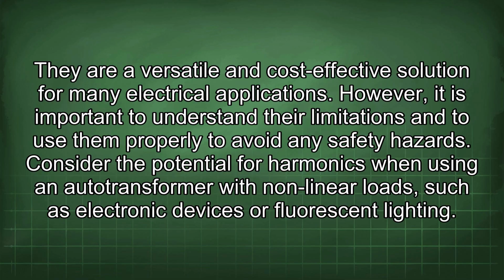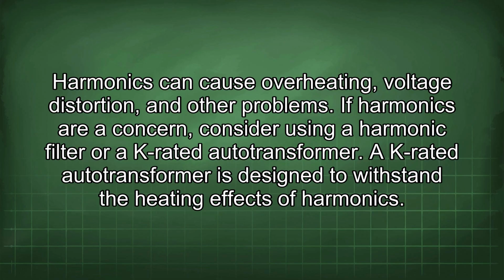Consider the potential for harmonics when using an autotransformer with nonlinear loads, such as electronic devices or fluorescent lighting. Harmonics can cause overheating, voltage distortion, and other problems. If harmonics are a concern, consider using a harmonic filter or a K-rated autotransformer. A K-rated autotransformer is designed to withstand the heating effects of harmonics.